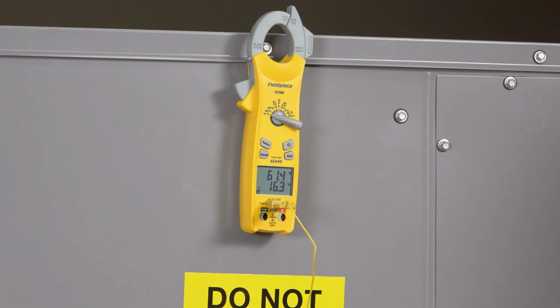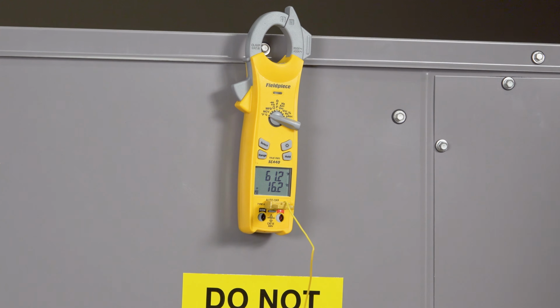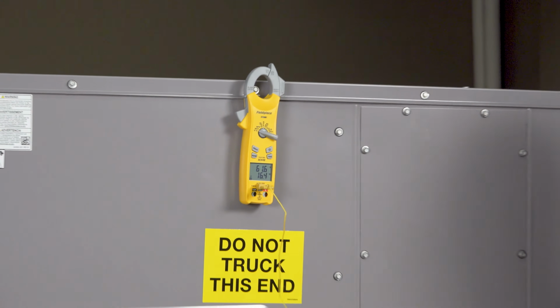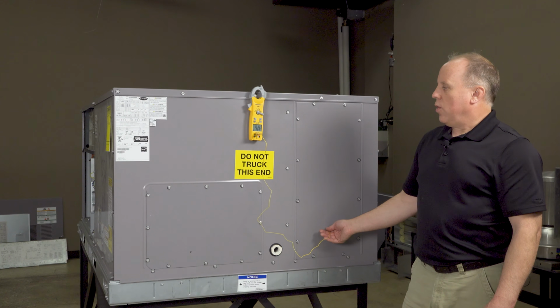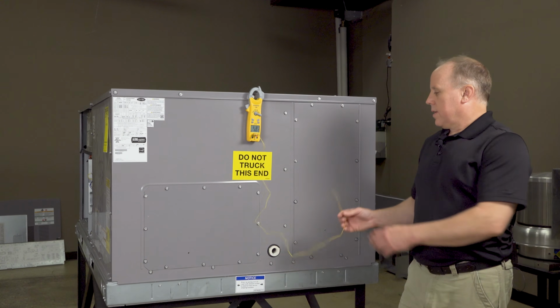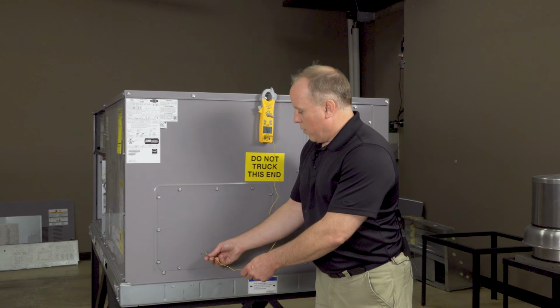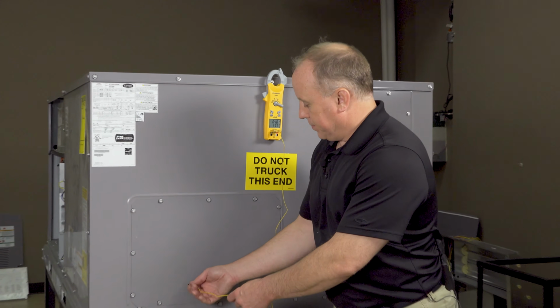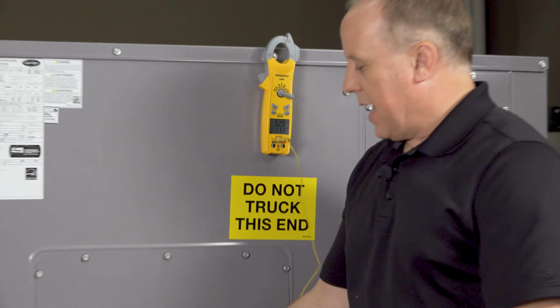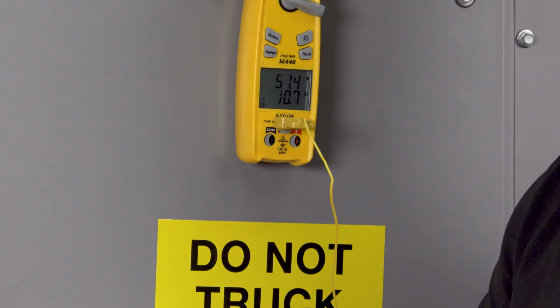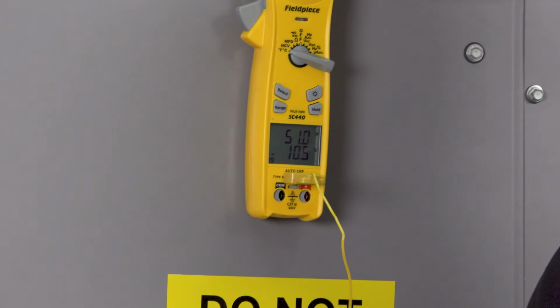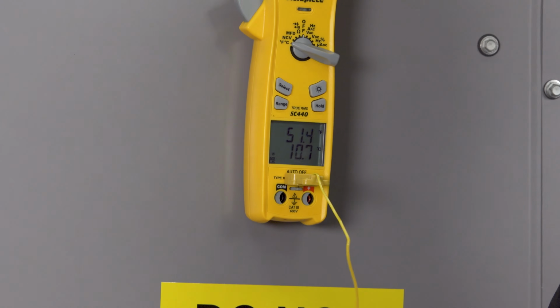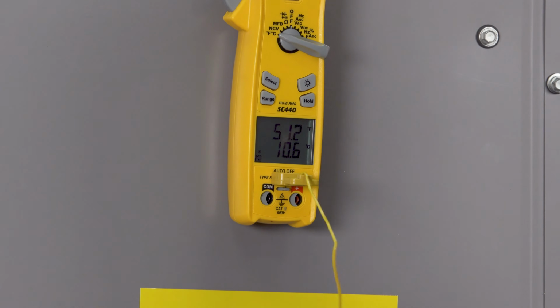This is direct. This is actually a lot more accurate for what the unit's doing because we're doing it at the unit than if we were doing it just below the unit in the ductwork. It's kind of holding there. So now I'm going to go into the supply side, which also when we're doing this, if we're doing it in the heating, we'd have to be careful because our heat exchanger is in here. So we've got to make sure we don't touch the heat exchanger with our probe.